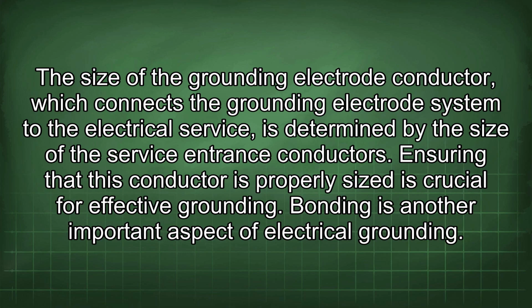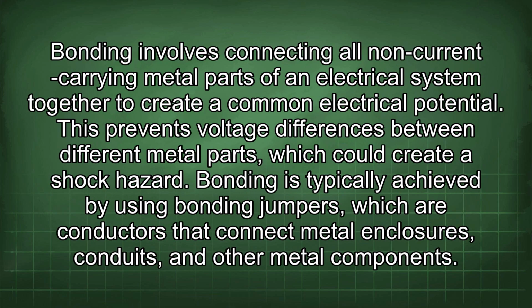Bonding is another important aspect of electrical grounding. Bonding involves connecting all non-current carrying metal parts of an electrical system together to create a common electrical potential. This prevents voltage differences between different metal parts, which could create a shock hazard. Bonding is typically achieved by using bonding jumpers, which are conductors that connect metal enclosures, conduits, and other metal components.